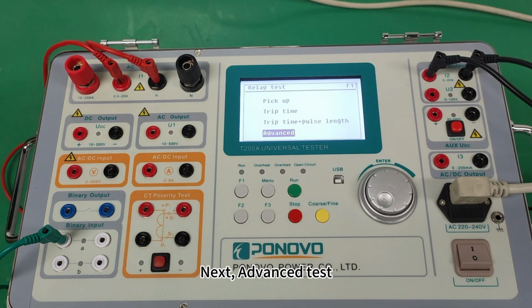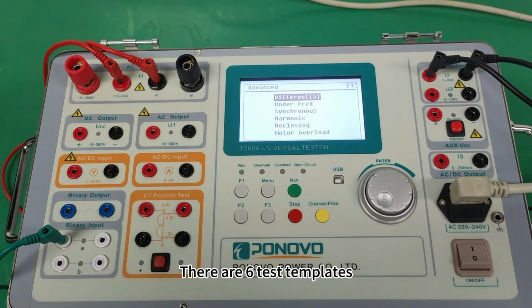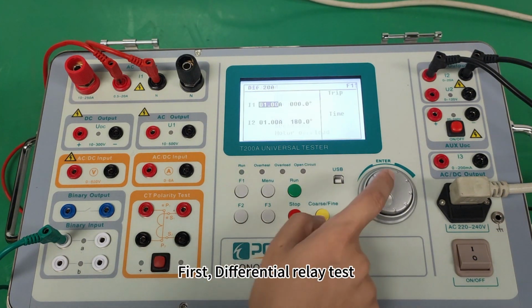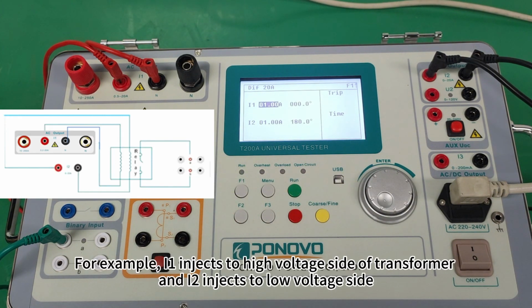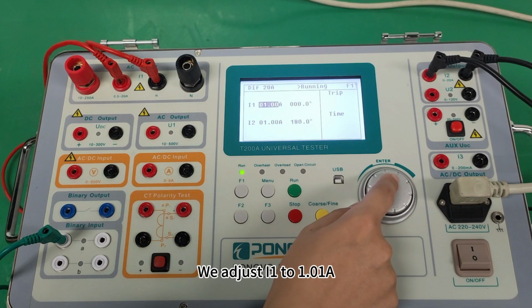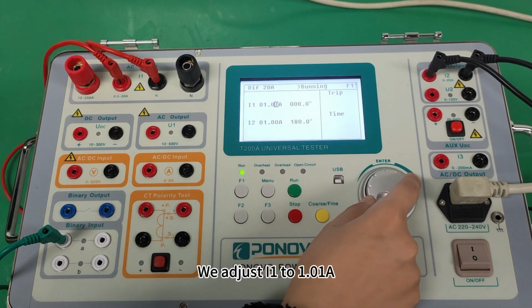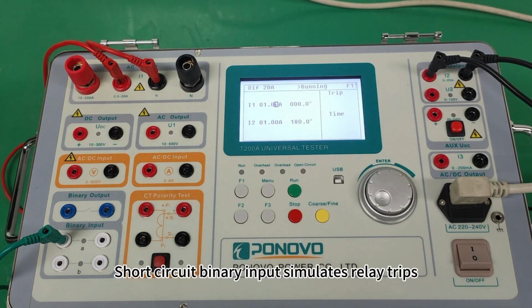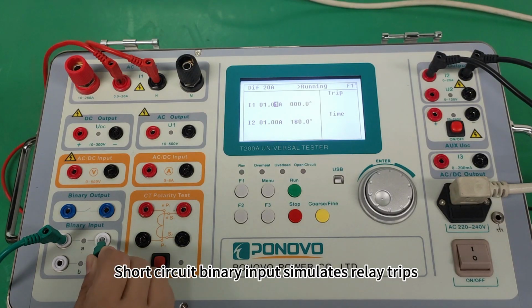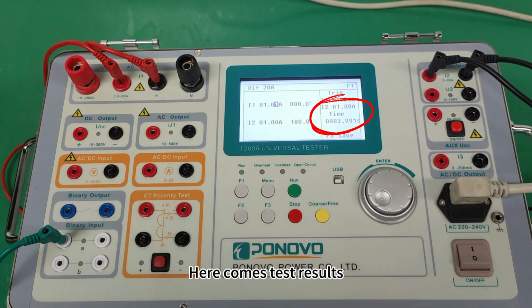Next, advanced test. There are 6 test templates. First, differential relay test. For example, I1 injects to high voltage side of transformer and I2 injects to low voltage side. We adjust I1 to 1.01 amperes. Short circuit binary input simulates relay trips. Here come test results.